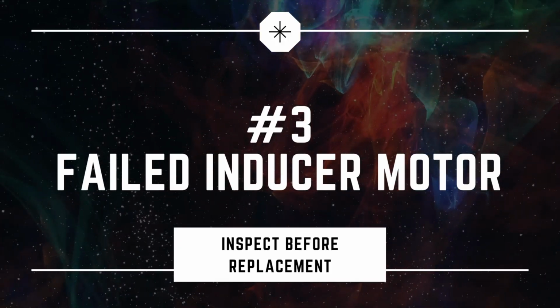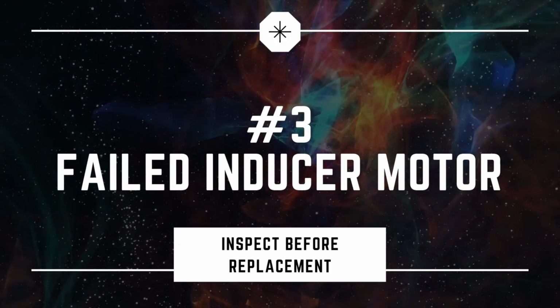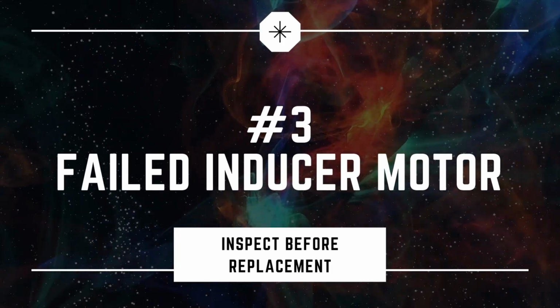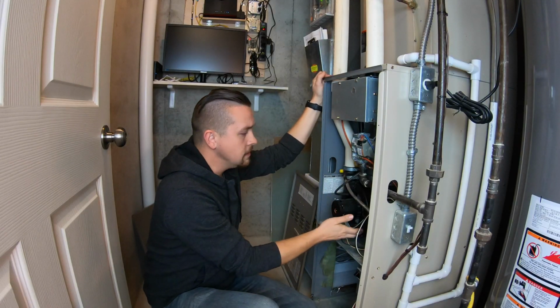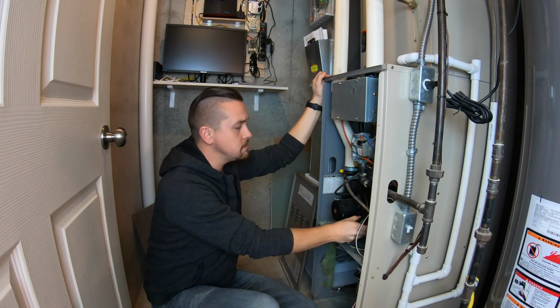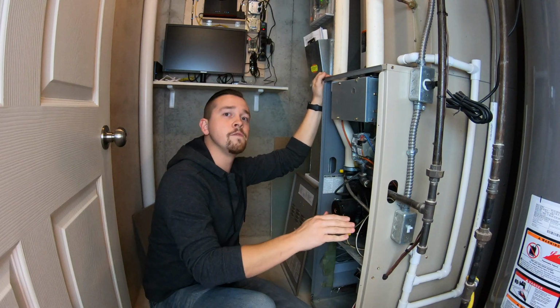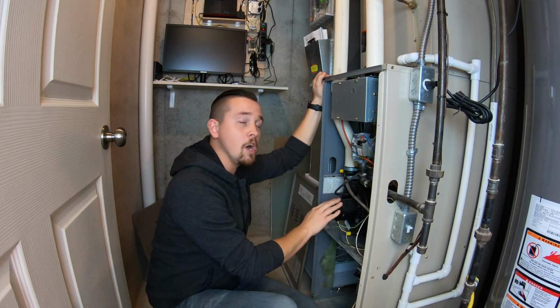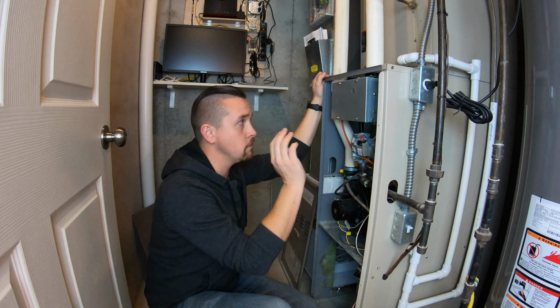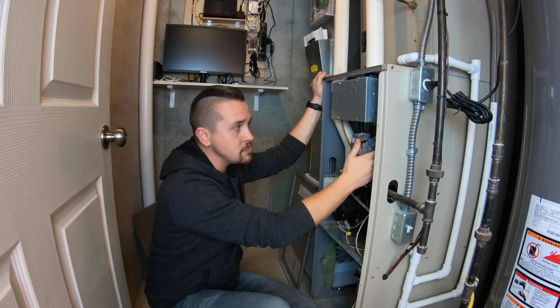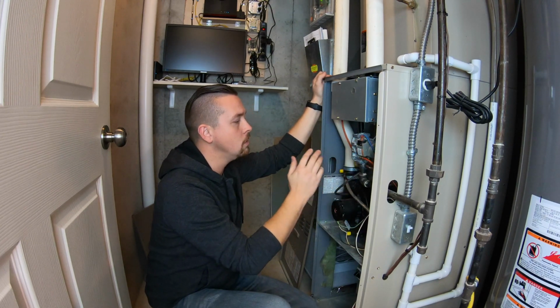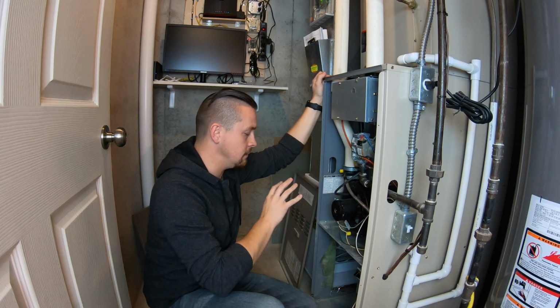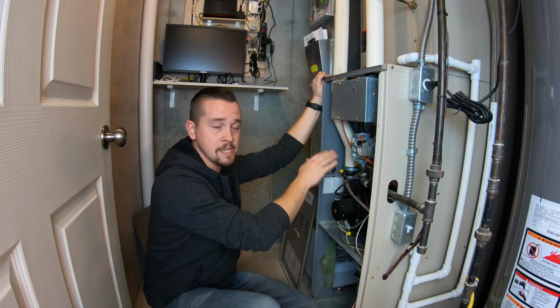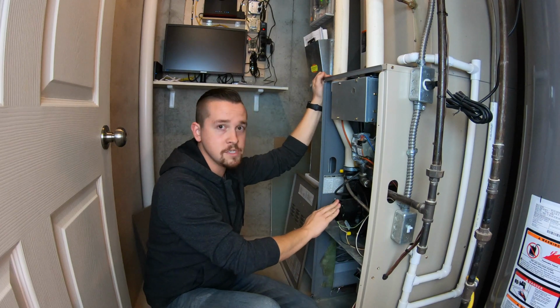Number three, a failed inducer motor. This motor right here is the inducer motor. It's connected to the inducer assembly. This is the exhaust motor for the system. And if this is not running, the rest of the furnace will not run either. The exhaust needs to be expelled from the house in order for the burners to light. So the pressure switch, which we talked about a moment ago, will not let the gas valve open or the igniter glow if this motor is not running.